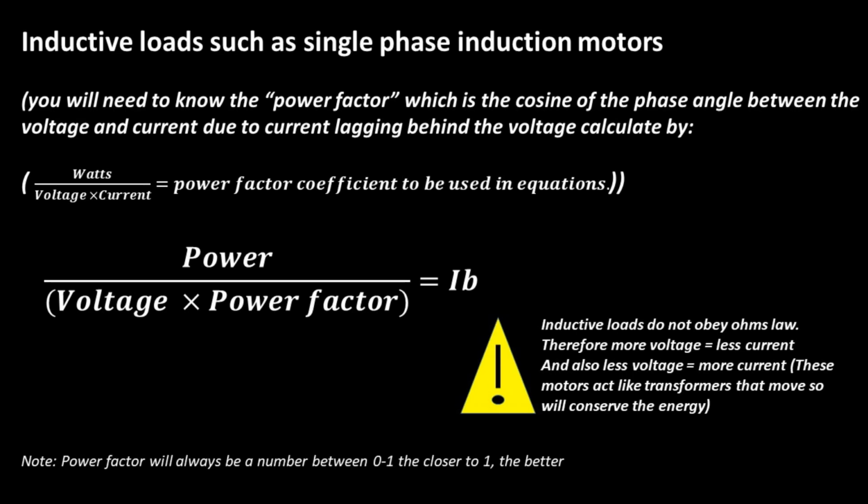Now, onto inductive loads such as single phase induction motors. You will need to know the power factor. The manufacturers give you that. It's normally on the data plate where we find all of our characteristics that we use to do our design. And it's just the watts divided by the voltage times that power factor.